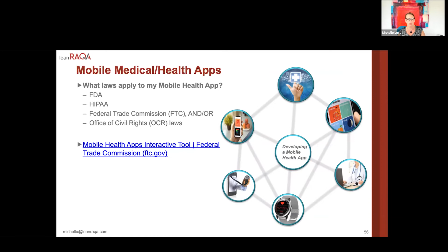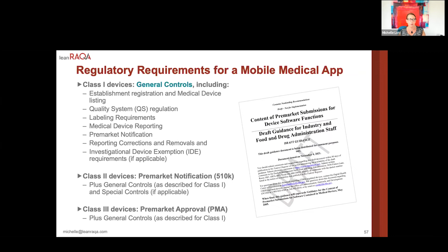So the regulatory requirements for a mobile app, like with some of these other types of technologies, can be considered Class 1 general controls that might be subject to a variety of different requirements like a quality management system, pre-market notifications, and your usual suspects. It could be Class 2 devices subject to a pre-market notification and 510(k), plus some level of general and special controls. Or it could be Class 3, which is going to be subject to pre-market approval and also those general controls.